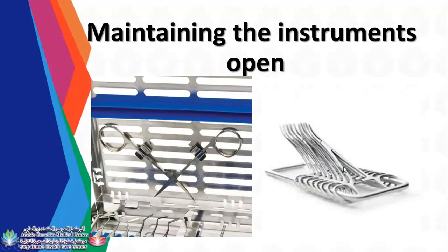Maintaining the instruments open. Okay, we have some devices. Once we put it in the rigid container, it depends, because there are times that the instruments have a specific container. For example, this is the specific container of this item. If you are placing this instrument in the rigid container or other containers, this item will maintain the instrument open, not that wide. It's just open. For this one, it is wide. It's okay because it's the feature of this tray.